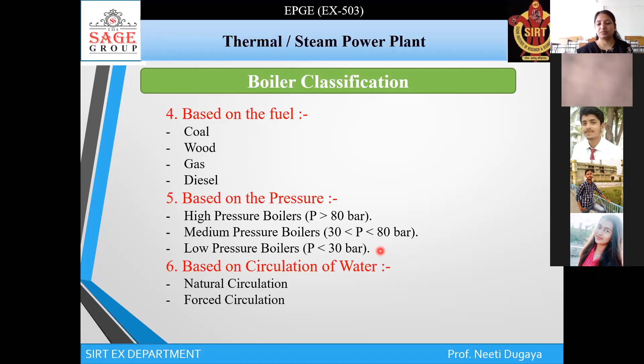This point you should keep underlined, because this could also be asked in the question of PSUs, that when the pressure is less than 30 bar, which boiler is being used. This could be asked in a question like this. So the fire tube boilers are preferred where the pressure is around 30 bars and the steam rate of 30 tons per hour is needed, and it is preferred because of the lower cost.